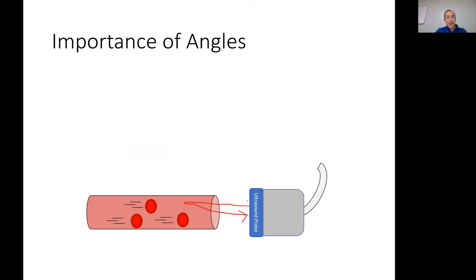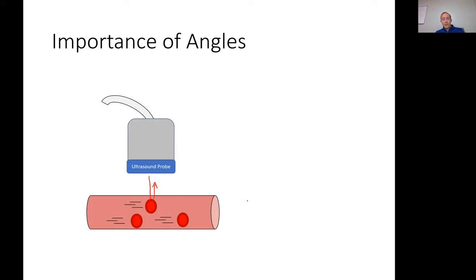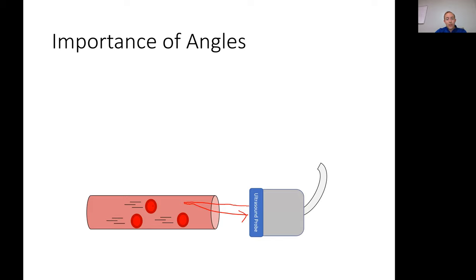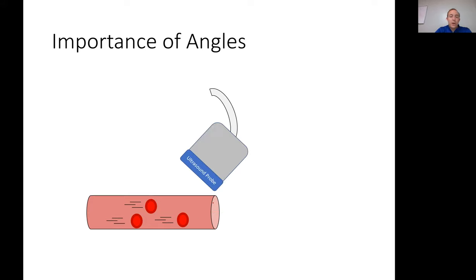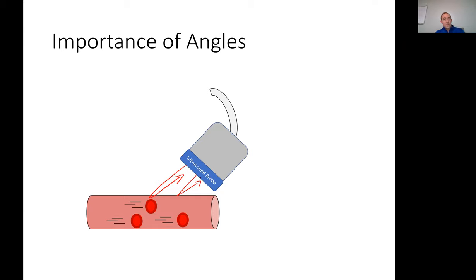If a car is moving head on at you and you throw a tennis ball, however fast it comes back is related to how fast the car is moving. But if you throw it perpendicular as the car goes down the street, it bounces back at the same speed you threw it — it doesn't pick up the car's movement. So to measure how fast something is moving, you have to hit it head on. This creates a conundrum: for good imaging and artery diameter we want one angle, but for blood velocity we want the other. The compromise is about a 60-degree angle of insonation.